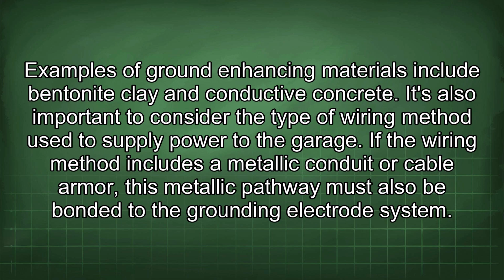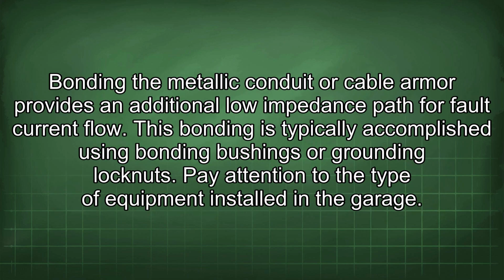It's also important to consider the type of wiring method used to supply power to the garage. If the wiring method includes a metallic conduit or cable armor, this metallic pathway must also be bonded to the grounding electrode system. Bonding the metallic conduit or cable armor provides an additional low impedance path for fault current flow.